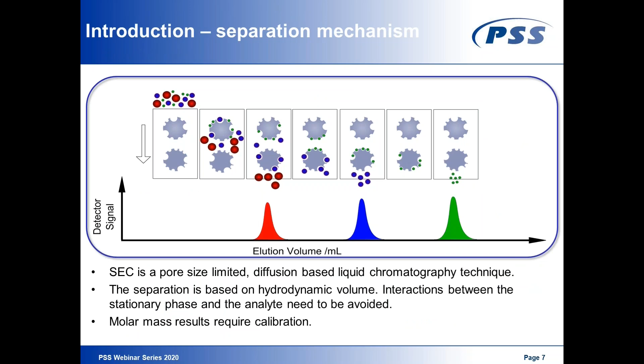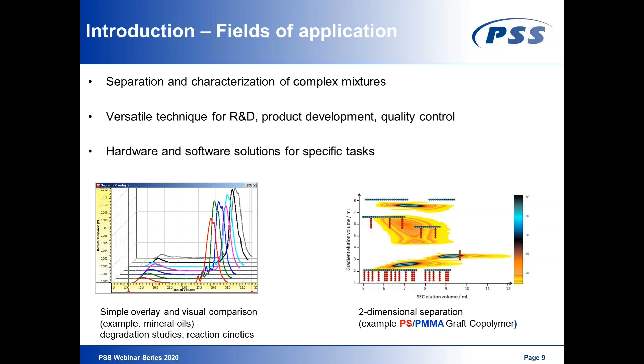In this case, for example, for a polystyrene-PMMA graft copolymer, it will make sense to use a UV detector for the polystyrene and an RI detector for both the polystyrene and the PMMA, and do dual detection here. Yeah, that would make sense. But what was the fear in that case? The question is basically, how do we account for the difference in molar absorptivity at different concentrations? In other words, the way I understand it, there is a fear that when you're using the UV detector, the concentration dependence will give you different UV traces.